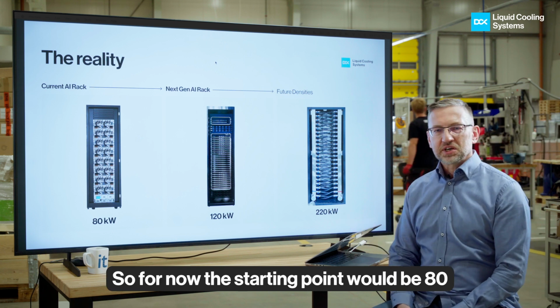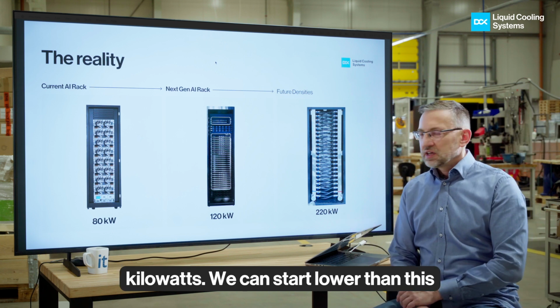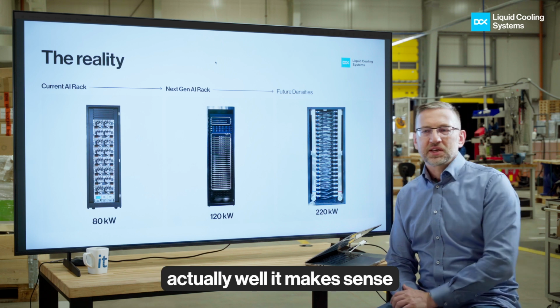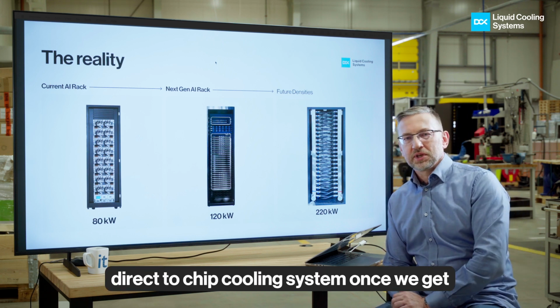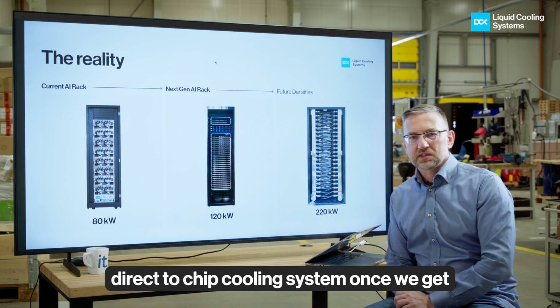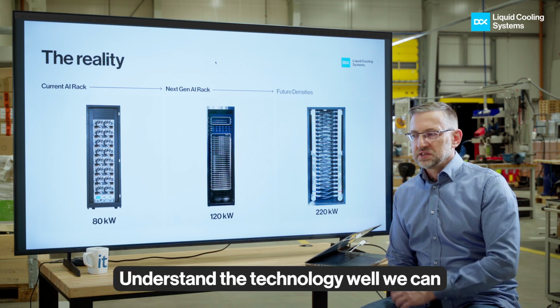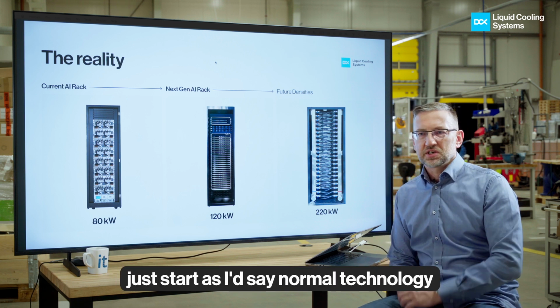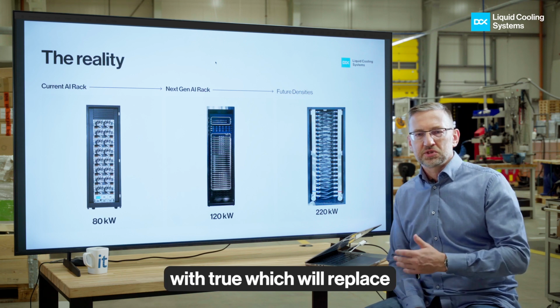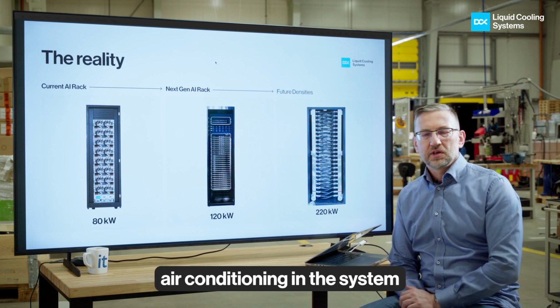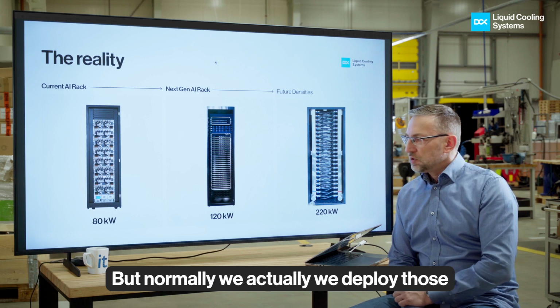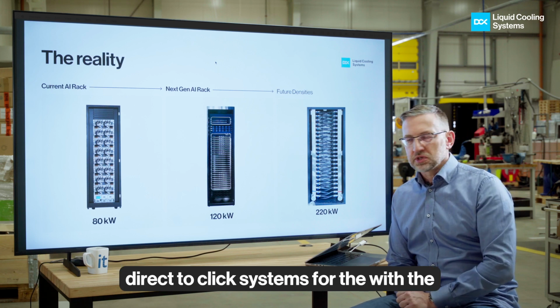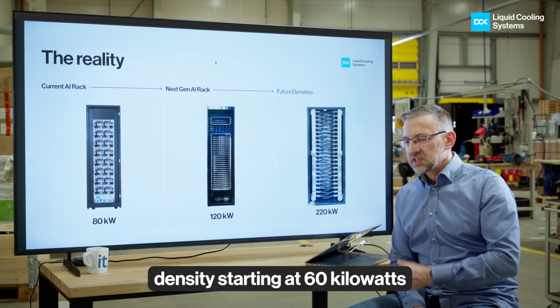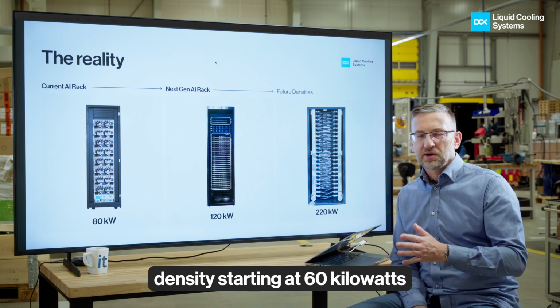So for now, the starting point would be 80 kilowatts. We can start lower than this actually. Well, it makes sense. It always makes sense to implement a direct-to-chip cooling system. Once we get more acquainted with it, understand the technology well, we can just start as, let's say, normal technology which will replace air conditioning in the system. But normally we deploy those direct-to-chip cooling systems with the densities starting at 60 kilowatts, 80 kilowatts.